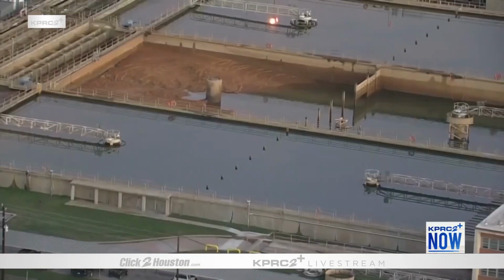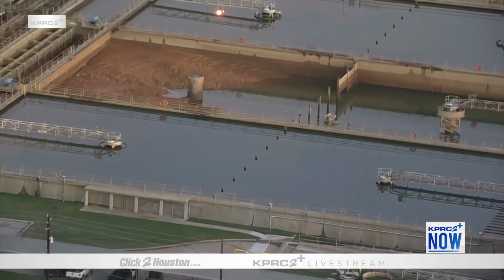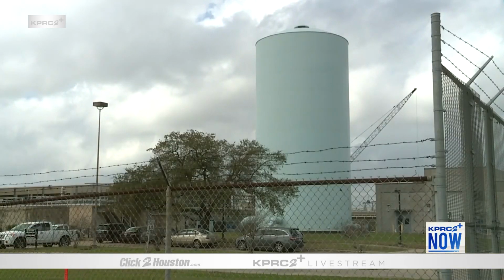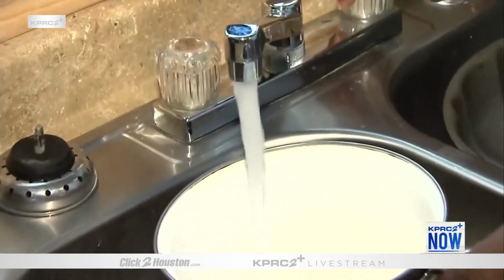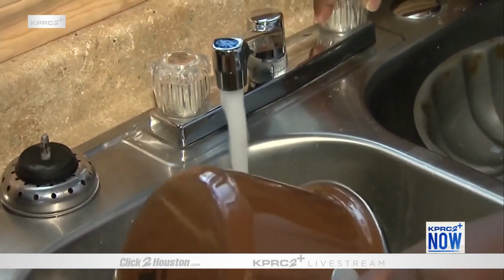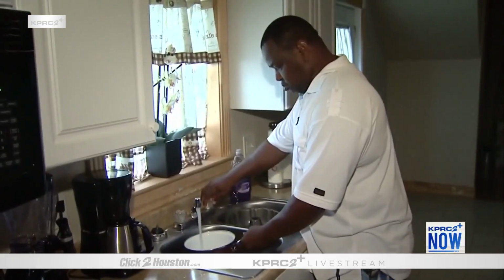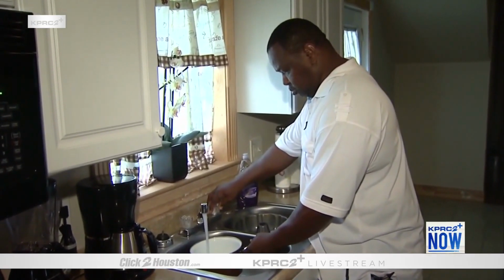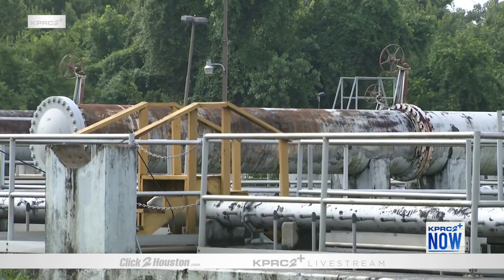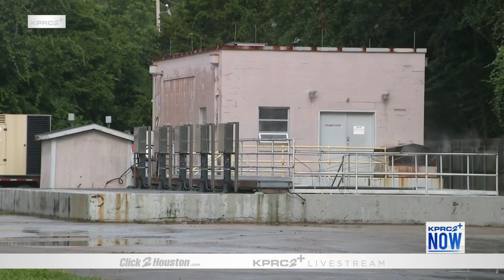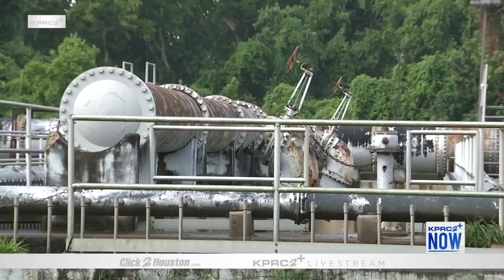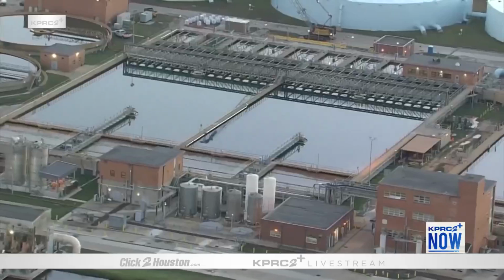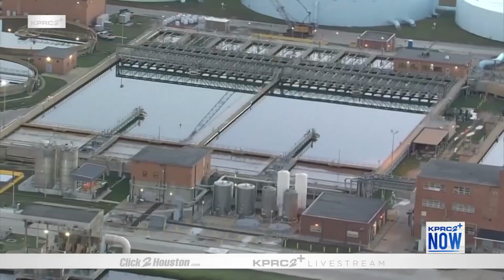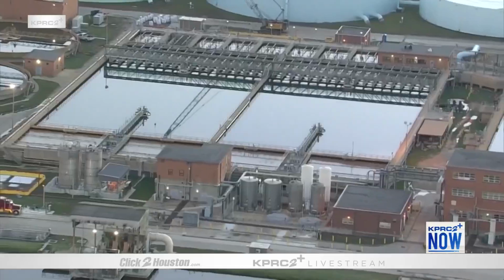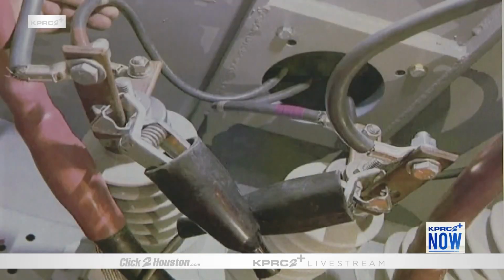City leaders say the facility needs millions in upgrades to prevent another system failure like the one that happened in November of 2022. A power outage at the plant triggered a citywide boil water notice, leaving millions of residents and businesses scrambling. Investigations found that a fault in a high voltage cable caused circuit breakers to trip, shutting down the facility's main transformer. A report from the mayor's office revealed the plant wasn't equipped to reroute power, making the outage far worse. But records show this wasn't the first time the plant faced issues.